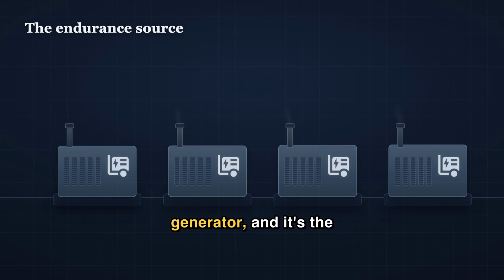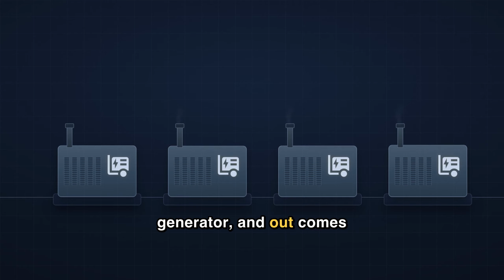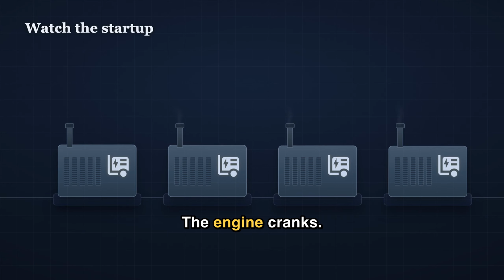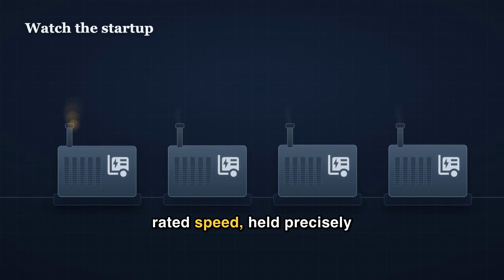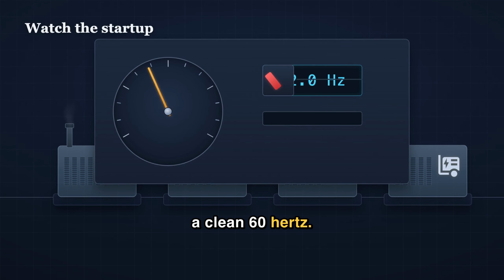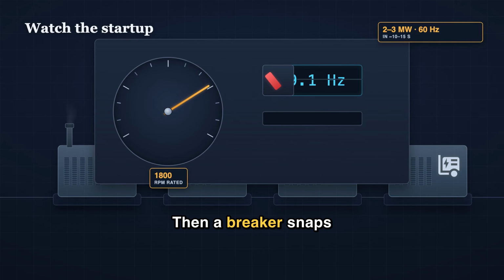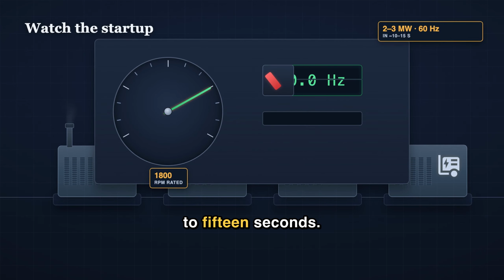Now the endurance source arrives. This is the diesel generator, and it's the muscle of the whole system. Each unit is a big engine, often 2 to 3 megawatts, and a facility runs several in parallel, like an engine room on a ship. The engine spins a generator, and out comes power identical to what the grid delivered. Watch the startup, because this is the 10 seconds everything else was buying. The engine cranks. It climbs to its rated speed, held precisely at 1800 RPM so the output lands at a clean 60 Hz. Voltage steadies. Then a breaker snaps shut and the generator accepts the full load, all inside roughly 10 to 15 seconds.